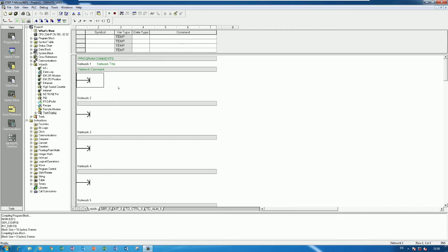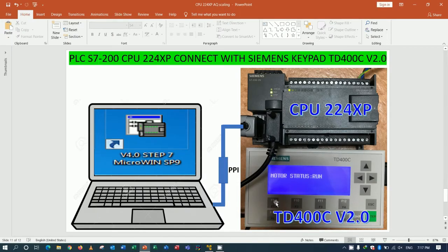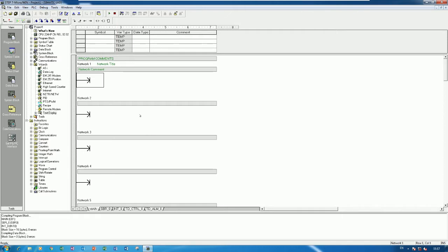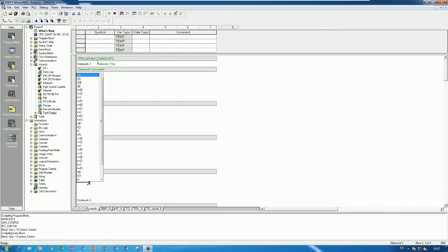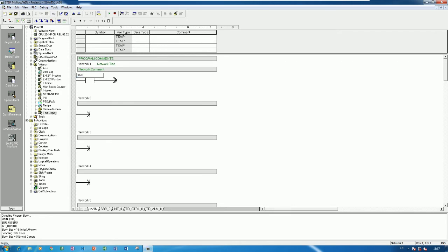The next step is to create the program that links with buttons F1 and F2 for start and stop of the motor condition. I will use SM 0.0 - I will use only one network for start, stop, and showing the alarm status. I need to use SM 0.0 for always-on.